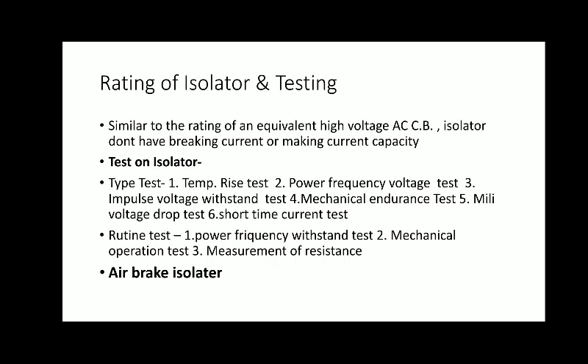There is no specific rating given here, but similar to the rating of an equivalent high voltage AC circuit breaker, its rating is the same. The rated insulation level, rated voltage, normal current rating and short time current rating are similar to those of an equivalent high voltage AC circuit breaker. If a line has a certain voltage circuit breaker, then the voltage of that circuit breaker is similar to the voltage rating of the isolator. An isolator does not have a breaking current or making current capacity.